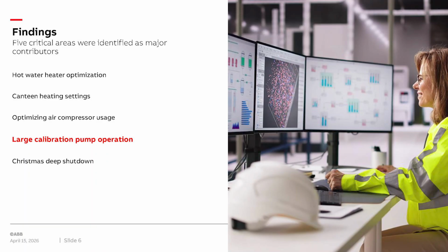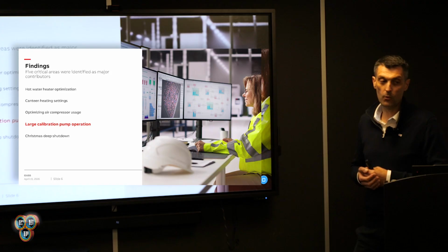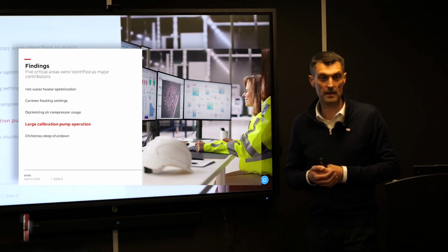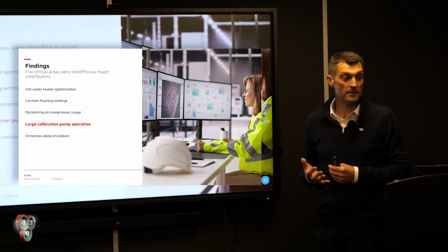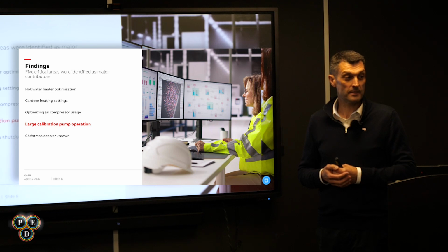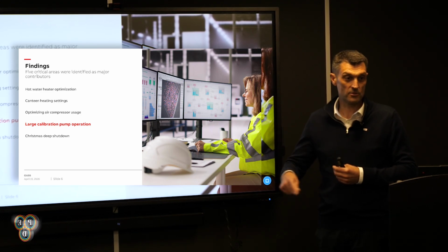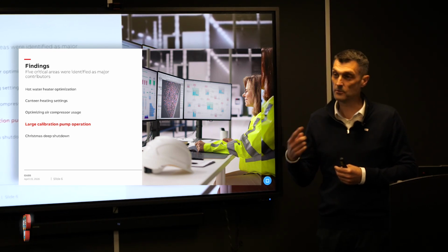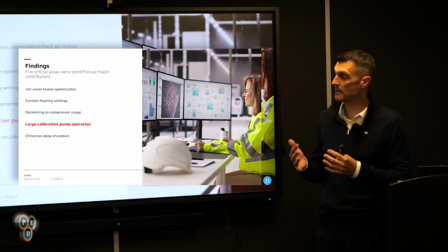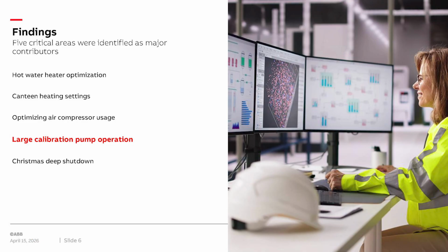After a 6-month period of having this system bedded in, we collected all the data, and some of what we found was silly stuff. The hot water heater was just left on permanent - it had a timer, but no one had ever set that timer up. So there's a device chewing up power 24/7 that doesn't need to be running that long. The canteen was running up until 8 or 9 p.m. every day, and they realised it was only used up until 3 p.m., so we saved 5 hours of energy usage per day.